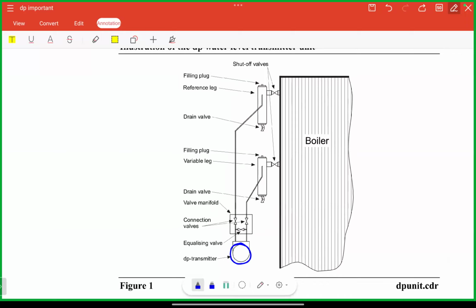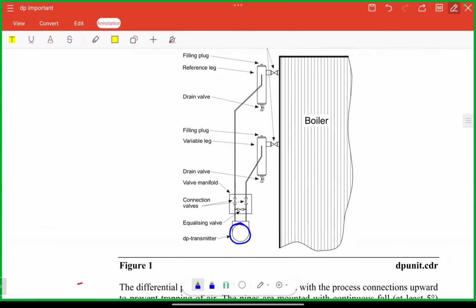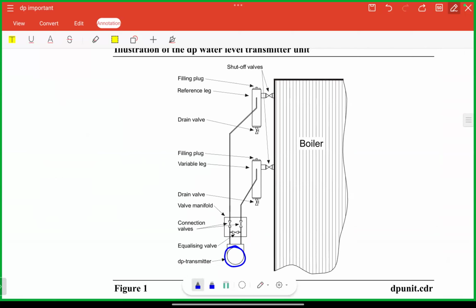Sir, what is the function of the equalizing valve? When you open the equalizing valve, what will happen to the pressure across your DP transmitter? Same. It is going to equalize. Yes, sir. During initial commissioning, we'll come to that one. At initial commissioning and calibration time, you may need to keep the pressure equalized on both sides. Okay, let's move further.